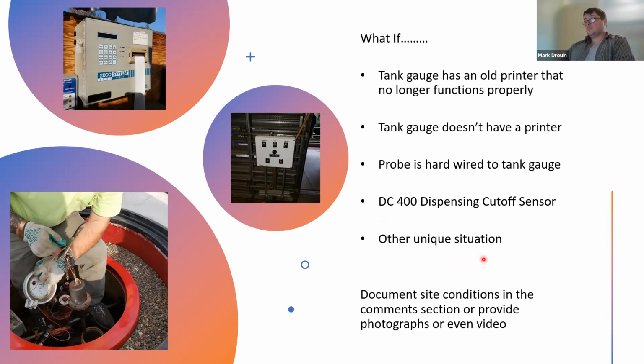I did an inspection a few years ago where the operator wasn't comfortable sounding the overfill alarm, but the contractor was there. So the operator filmed the contractor hitting the Veeder-Root buttons to sound the alarm. The alarm went off, I could hear it, and they turned it off. So it was just evidence that the alarm worked the proper way that day.